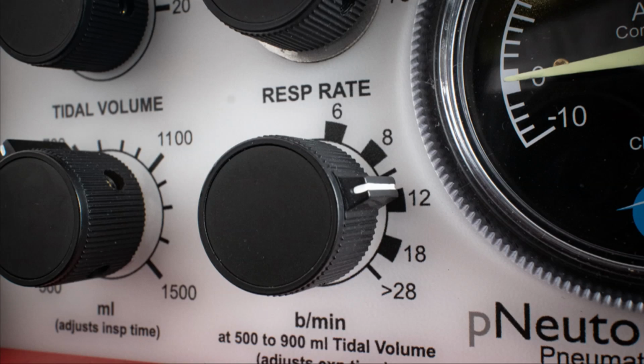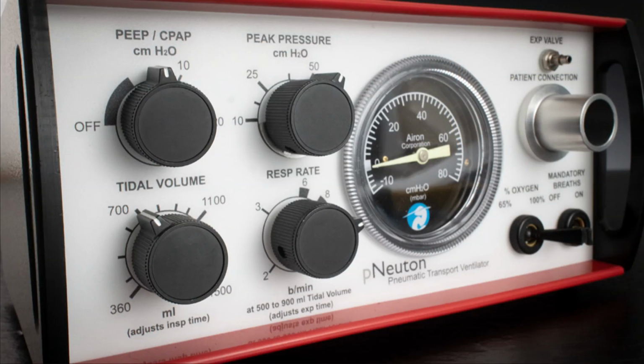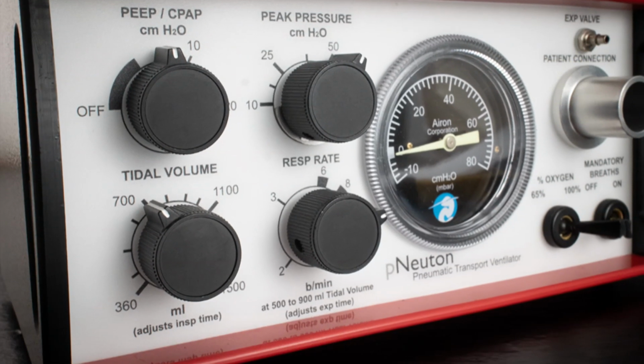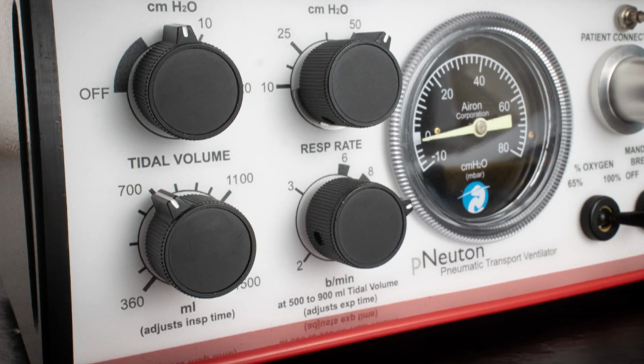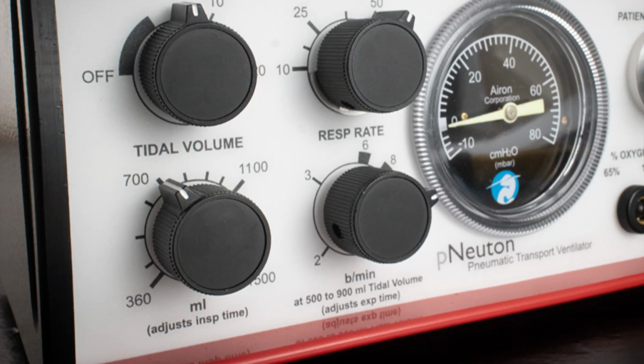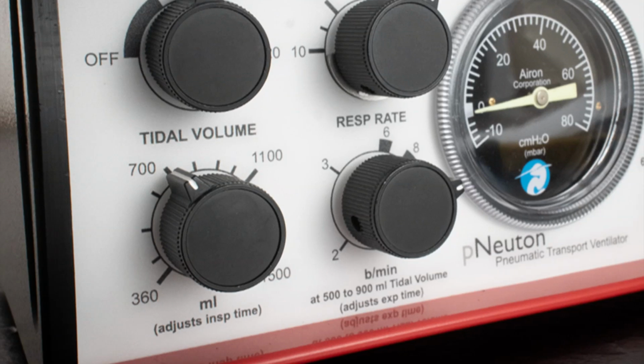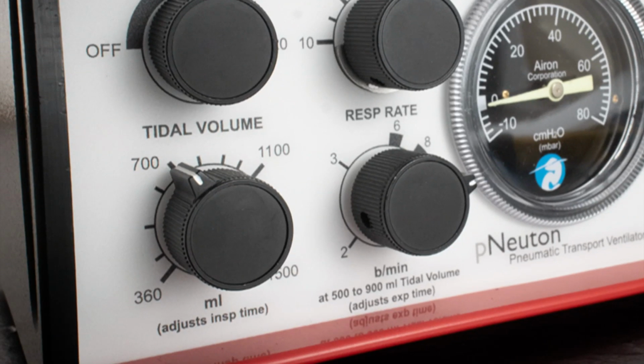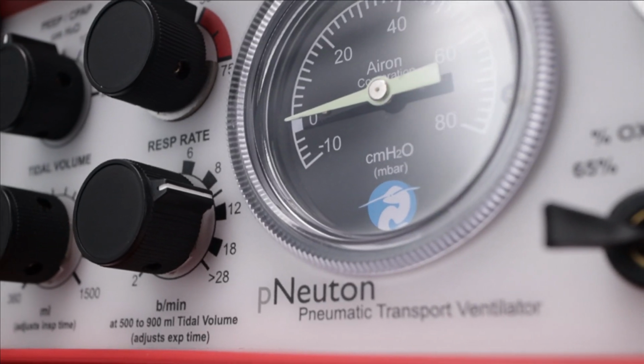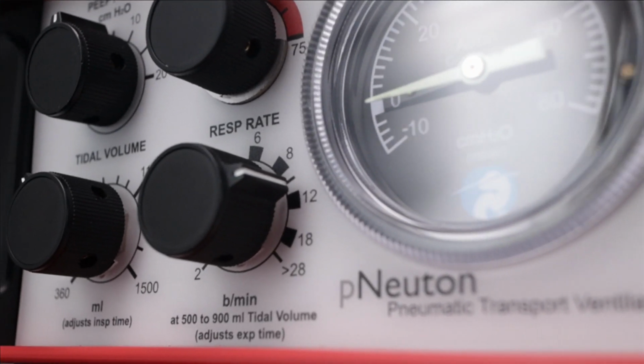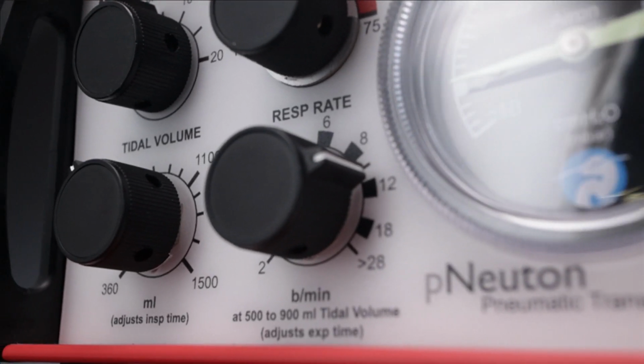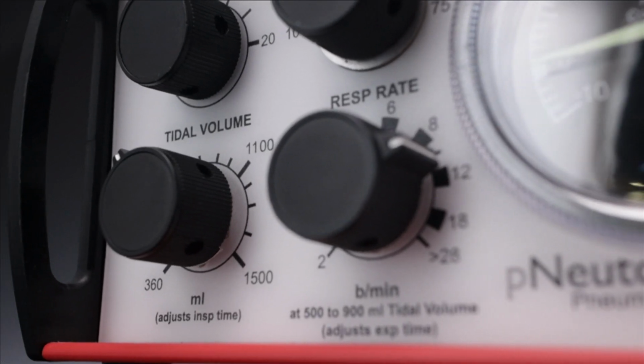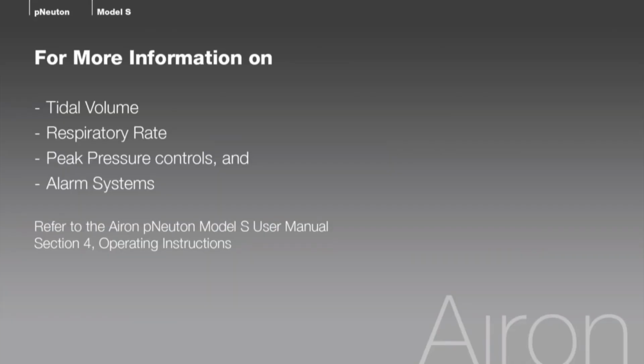of tidal volume. Let's discuss the basic operation of the tidal volume and resp rate controls. As a pneumatic ventilator with a peak flow that remains constant, when you change the tidal volume, the inspiratory time changes. It is recommended that you set the tidal volume first and then your desired resp rate. Changing resp rate changes expiratory time. For further information, we refer to the User Manual, Section 4, Operating Instructions.